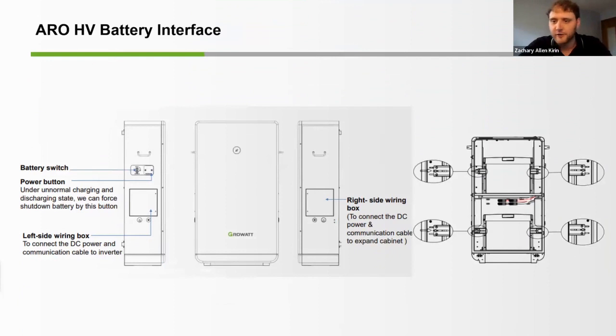Here we can see the interface of the ARO high voltage battery cabinet. The product has a built-in DC disconnect switch to mitigate those installation costs and is plug and play ready with the Growatt inverter. The left side of the wiring box connects the DC power and communications to the inverter, and the right side of the wiring box allows for that battery expansion.